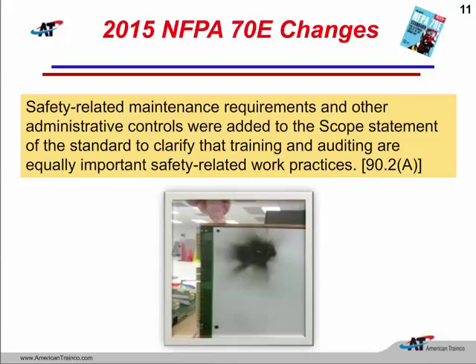Okay. Also, they really wanted to stress the importance of maintenance. So some safety-related maintenance requirements and other controls were added to the scope, and we're going to see that this will include additional training and especially auditing. Auditing is going to be very important because if we actually are practicing the safe work procedures, but we have not audited that, we have not documented it, then it becomes a moot point. We have to have documentation, we have to have forms in place that the training was given and the training was understood by the qualified worker, and we're going to go out and audit that. That was placed in the scope of this document to really give us an idea that the NFPA technical committees believe that training and auditing are extremely important. So they put that in the scope of the document to impact all of the 2015 NFPA 70E.